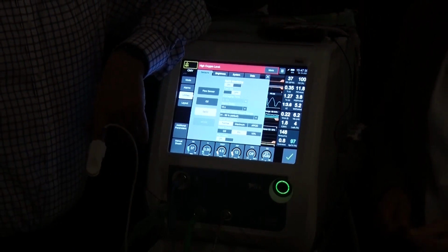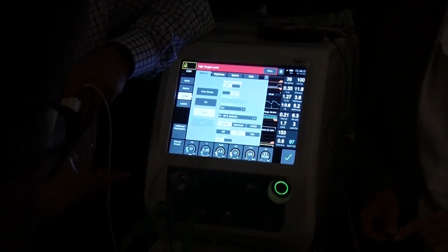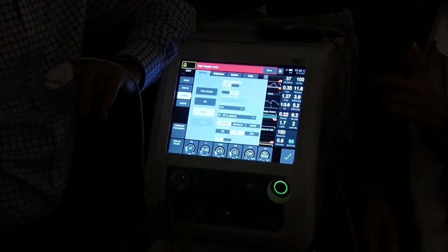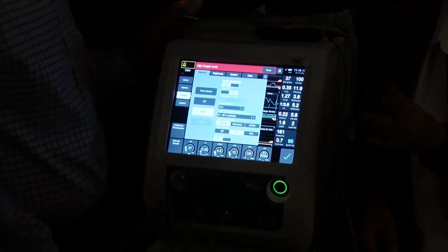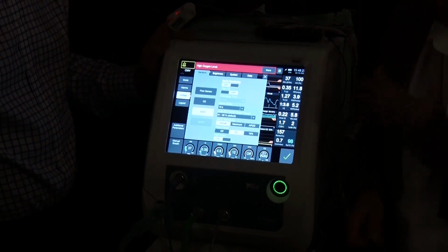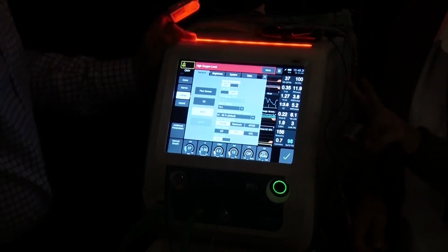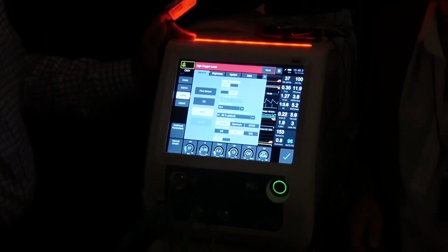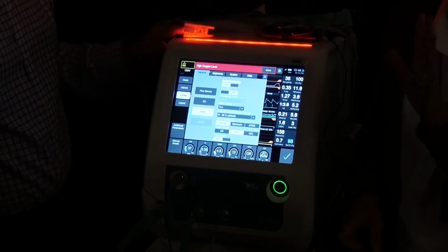Do you want to keep doing more things, or are you so tired you have to go? What should be the ideal time between adjustments? It is 10 seconds for all the others. So this one will be defaulted to 2 to 4 seconds, because the minimum time between two adjustments is 1 second, so you need very fast feedback. You have to be cautious if you start Oxygenie and you have SpO2 drops, because you will read some very different data on the ventilator and on your monitor. Your monitor is most of the time averaging over a longer period.